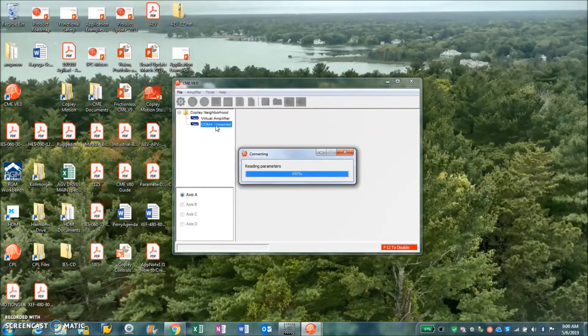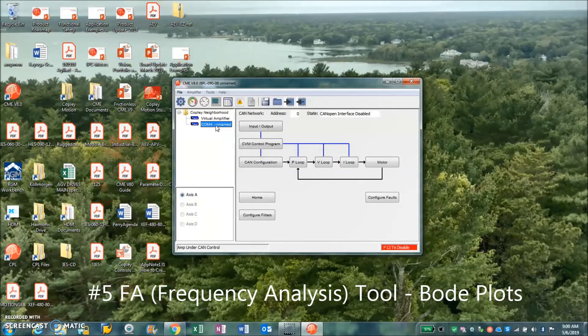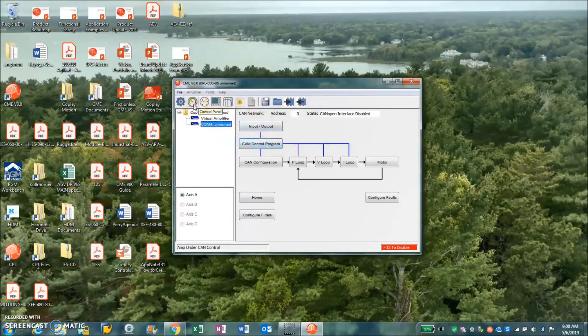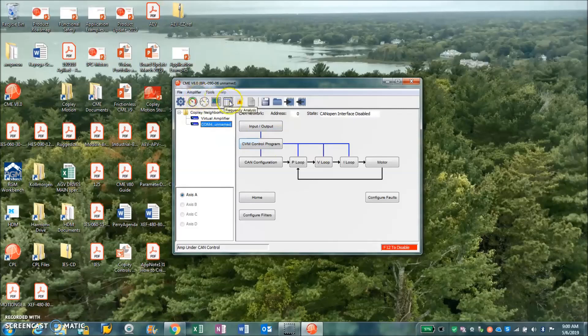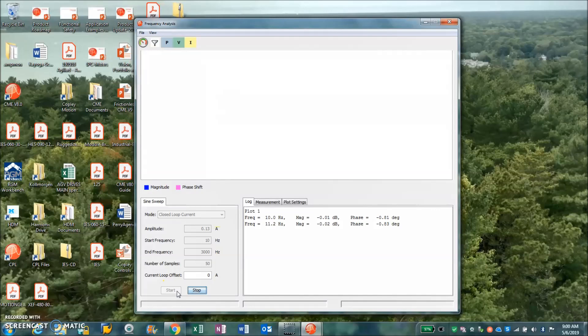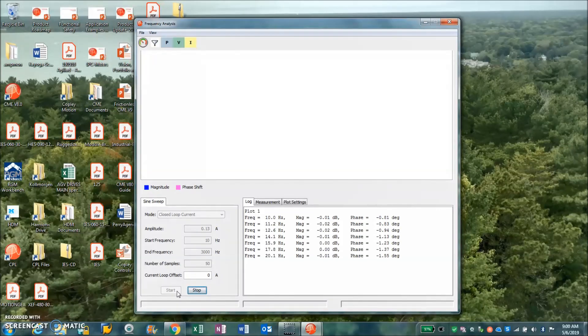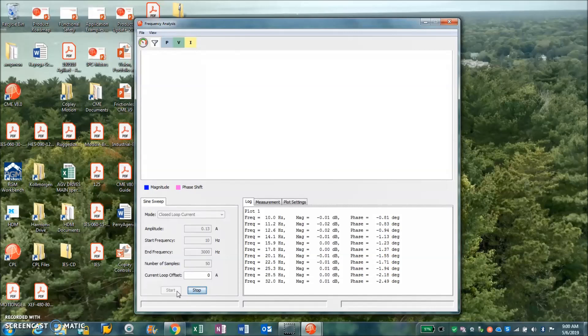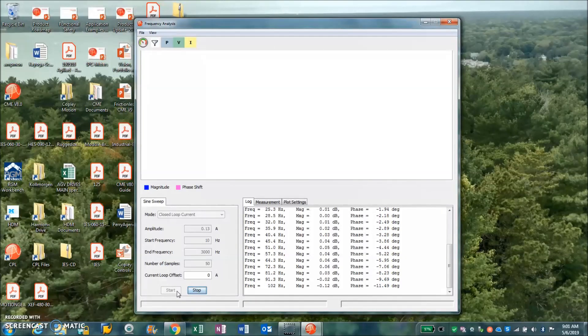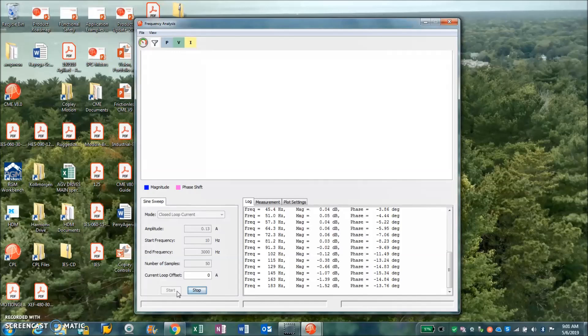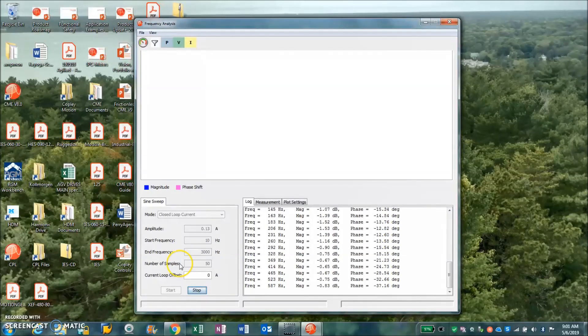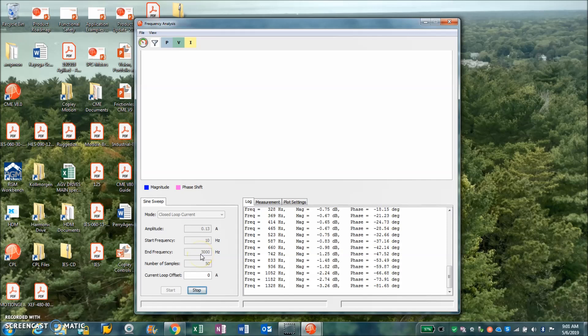Another interesting feature is the frequency analysis tool. So I'm going to call this number five for interesting things. Frequency analysis tool allows you to go through frequency analysis for various loops. So the drive does the Bode plot, it does the excitation frequency, it looks at the gain magnitude and phase angle. When the sweep is done, you can look at the frequency response of the current loop here.